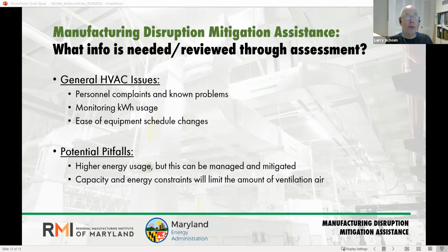And so we use that as a starting off point sometimes for identifying a problem, whether it's with indoor air quality or with energy. And of course, with indoor air quality, there are certain things that can be measured, like PM2.5 and volatile organics. But energy is really easy. Well, I shouldn't say really easy, but it's something we can measure with a great degree of precision. It's easy if the meter is in there. It's not always easy to put the meter in. So monitoring what is already being measured is a very important and quantifiable thing. And then how easily can you change set points and schedule? I mentioned full automation as opposed to something that's more manual.